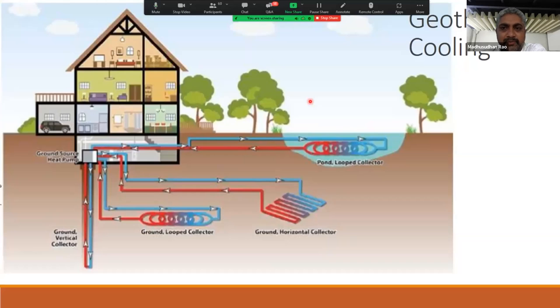That doesn't change. But your output of the geothermal bore will depend, among other things, definitely on the temperature of the soil. If the average temperature of the soil in Paris is 15 degrees and in Delhi is 27 degrees centigrade, then the same length of bore will give more output in Paris than in Delhi. Therefore, you need to dig deeper. So in Paris, let's say you are happy with a 50 meter or 40 meter bore; in Delhi, to get the same output, you need to go for a 100 or 120 meter bore, which again increases your cost, right?